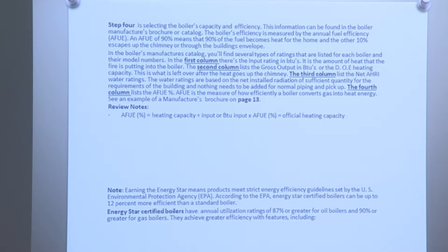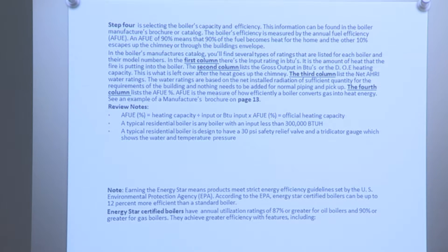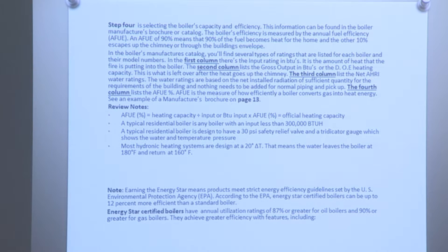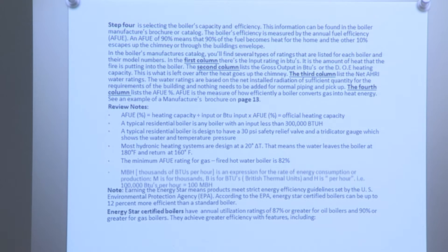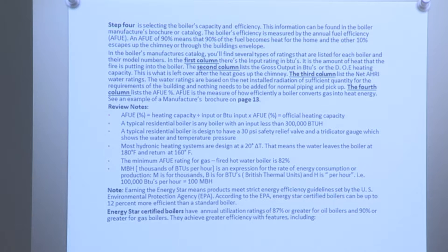AFUE percent equals heating capacity divided by BTU input; BTU input times AFUE percentage equals official heating capacity. A typical residential boiler has an input less than 300,000 BTUs. It is designed with a 30 PSI safety relief valve and a tridicator gauge showing water temperature and pressure. Most hydronic heating systems are designed at a 20 degree delta T, meaning water leaves the boiler at 180°F and returns at 160°F. The minimum AFUE rating for gas-fired water boilers is 82%. MBH equals 1,000 BTUs per hour — M is for 1,000, B is BTU, H is per hour — so 100,000 BTUs per hour equals 100 MBH.